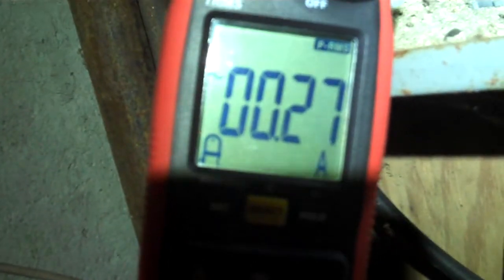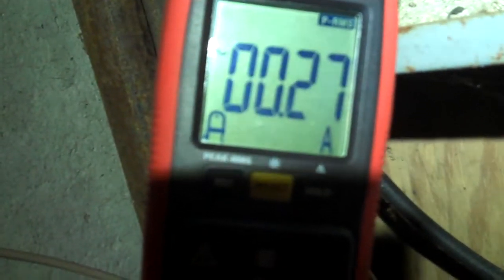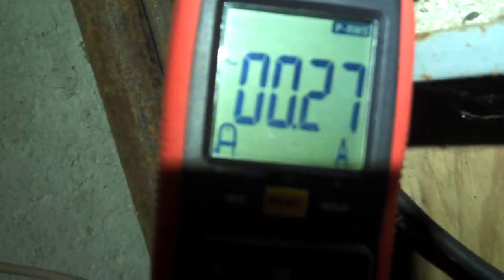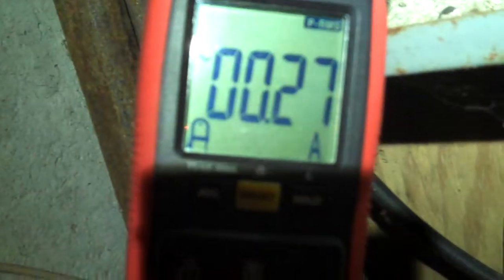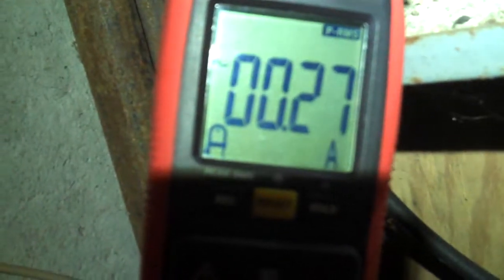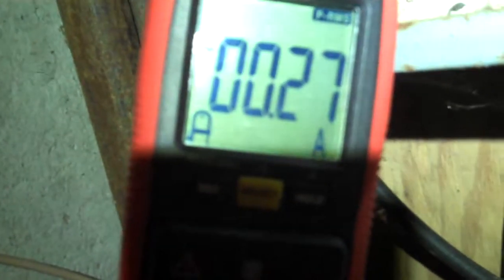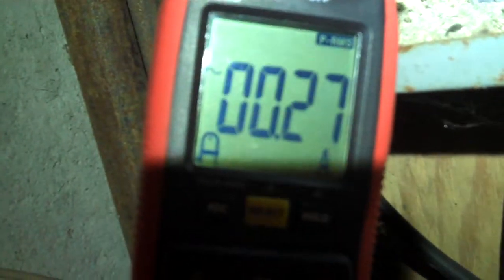Okay, Maureen, go ahead and run water. This will trigger when water is running, and then when it sees that the pump is turned on, it'll measure the inrush current. Right now it's reading 0.27. I'm not quite sure where that particular number is coming from. There are two legs of power on the 240 volt pump. So what I'm going to try to do is measure it on one leg, and then measure it on another leg.